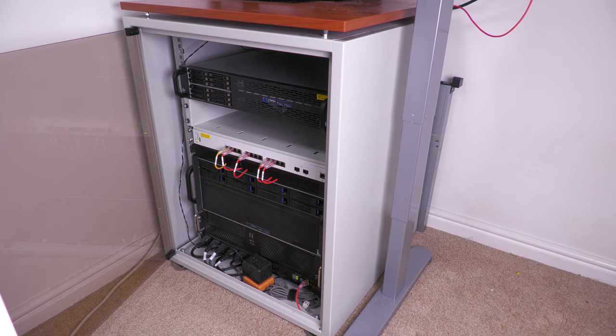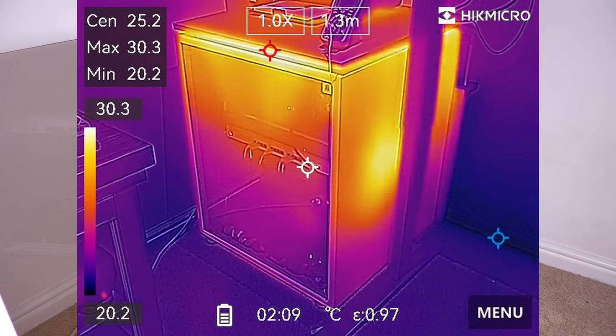And if we take a look at a thermal image I took, you can see that the sides of the rack do get quite hot. These were taken with the rack fan turned off, and all the heat was being dissipated through the sides of the rack. And you can see that the top of the rack gets quite hot, where it'll be radiating out heat. The sides are quite hot, radiating out heat.